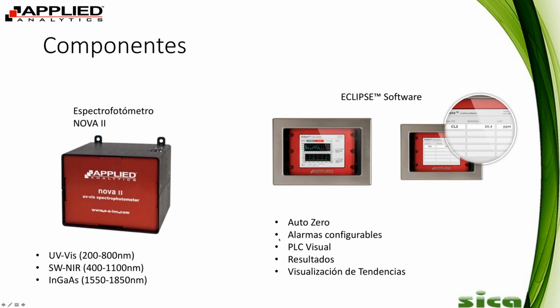There's auto zero, so that will protect the analyzer against any drift or anything like that. Auto zero happens every 6 to 8 hours, depending on customer preference. There is manual span check. So the span check is necessary to verify your measurement. The auto zero is what keeps the accuracy and the resolution of the measurement, but the span check is what verifies the measurement. It's what validates it. So it's what tells you that the analyzer is reading correctly. So span check is done, again, depending on the customer. We recommend every other month. Some people do it every month. Some people do it every week. Some people don't do it. So that's a customer thing, really.